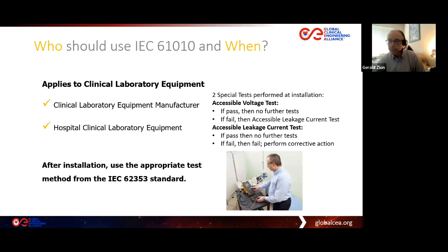All right, so if it did not pass the accessible voltage test, then we must perform the accessible leakage current test. If it passes that test, then again, no further tests. We have the measurements we need, and we can put it into clinical use. But if it fails this test also, then it has failed and we have to do a corrective action and then repeat the tests, definitely before go live, and certainly before that equipment ships from the manufacturer of that clinical laboratory equipment.